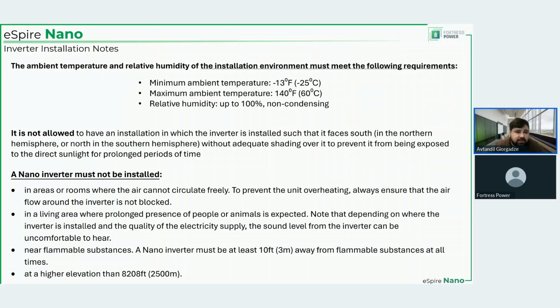Another thing that has to do with temperature is that we are not allowing installations in which the inverter is south-facing, right? Because we're in the northern hemisphere, on the south wall, especially in the summer, and maybe fall too, the inverter will be exposed to direct sunlight for a prolonged period of time, which can fail the HMI screen very quickly and overheat the internal components. And remember, this is an air-cooled unit. This is not liquid-cooled. So perhaps it does not have as much cooling capacity as your car would with a radiator, right? So it is very important that if it is installed on the south-facing wall, there is adequate shading so the unit is not exposed to the direct sunlight.